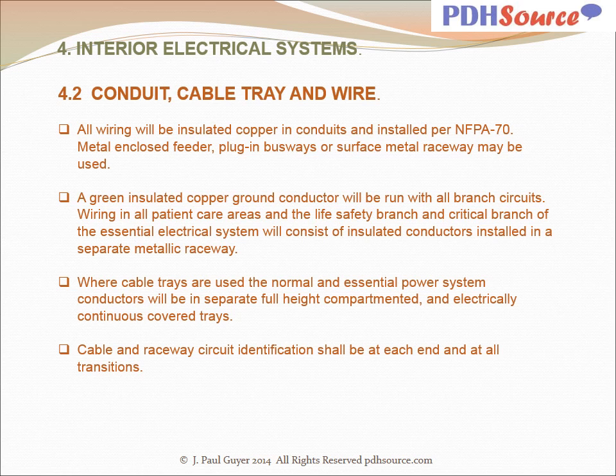All wiring will be insulated copper in conduits and installed per NFPA 70. Metal enclosed feeder plug-in busways or surface metal raceways may be used. A green insulated copper ground conductor will be run with all branch circuits. Wiring in all patient care areas and the life safety branch and critical branch of the essential electrical system will consist of insulated conductors installed in a separate metallic raceway. Where cable trays are used, the normal and essential power system conductors will be in separate, full-height compartmented and electrically continuous covered trays. Cable and raceway circuit identification shall be at each end and at all transitions.